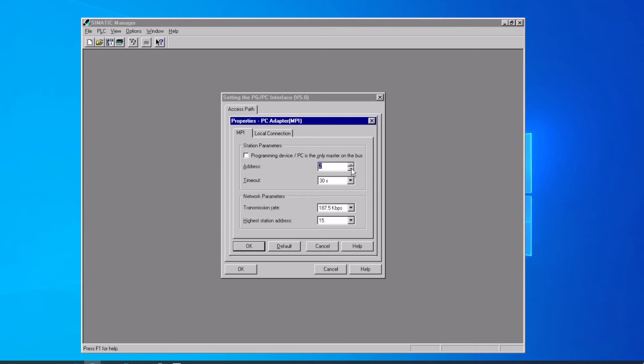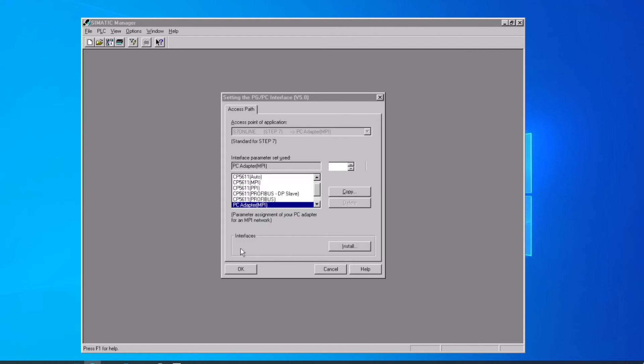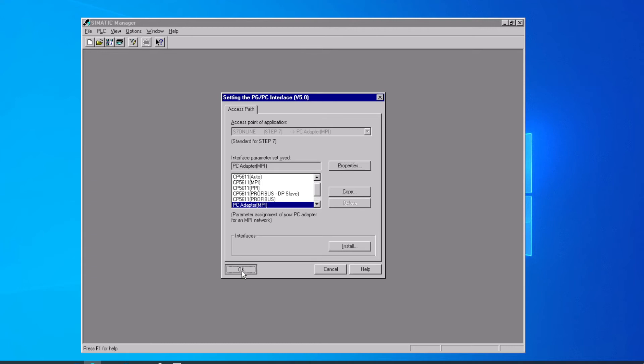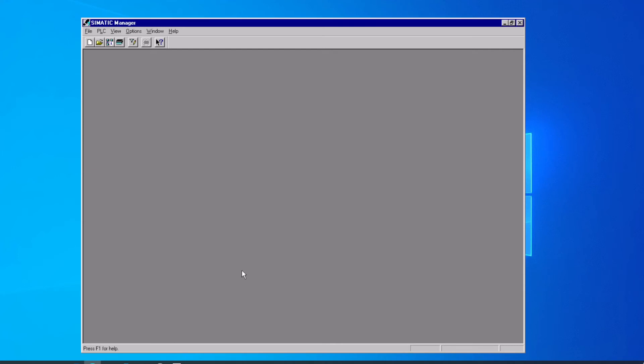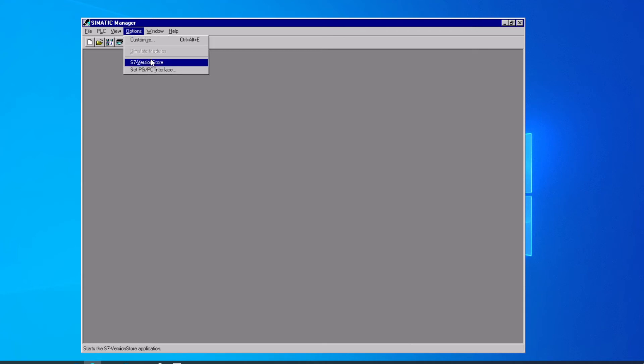We can also set the address, the MPI address of this local programming computer. This would normally be zero, but the only time you'd want to change that is if you had multiple programming computers on the network where they could each have their own unique interface. So we just keep clicking okay to work our way back out of the windows. We've got now the interface installed, and that is our communication option.